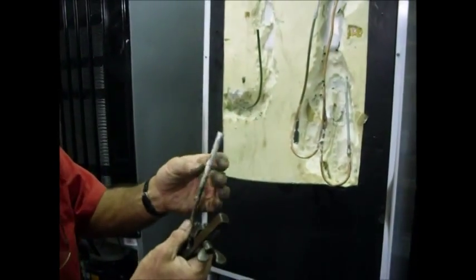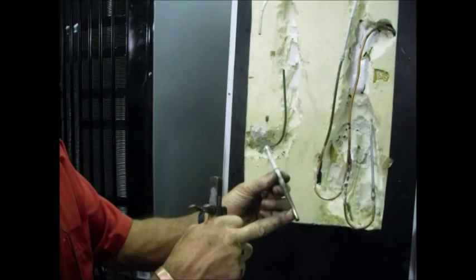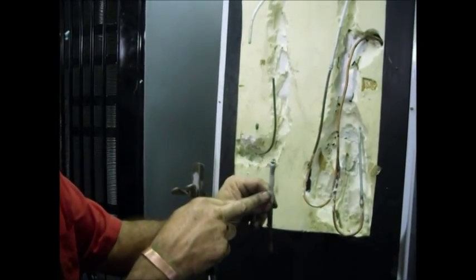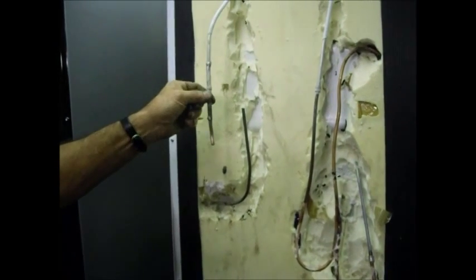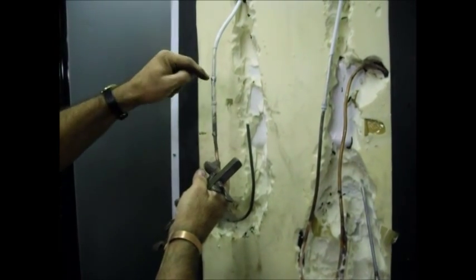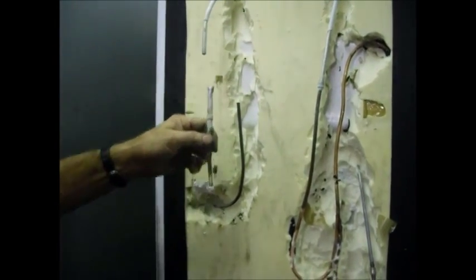Now how we do that is we get these little pieces of tubes that we scavenge from old fridges which is aluminium and there's copper and there's a copper to aluminium joint there. We prepared it so that this aluminium fits on there and we do aluminium weld here. There's copper and we can join a nice copper pipe.